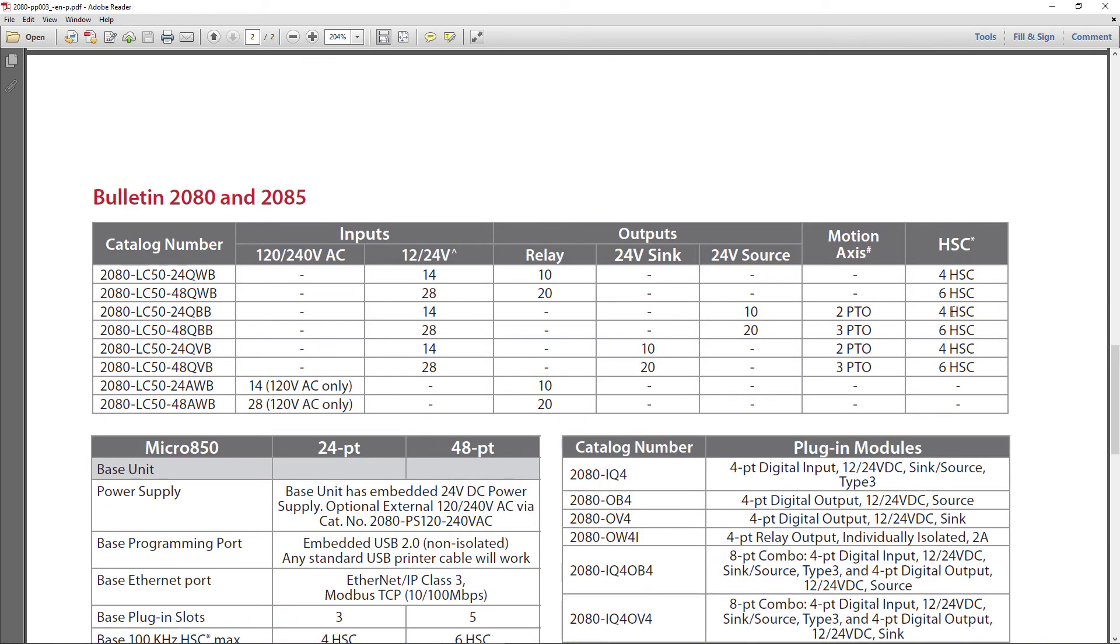If you tell an axis to make a move and it requires 1200 pulses from a PTO output, it's going to pump out those 1200 pulses regardless of where the processor's at in a scan.